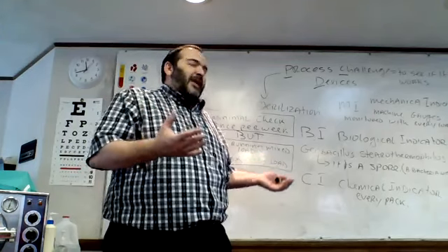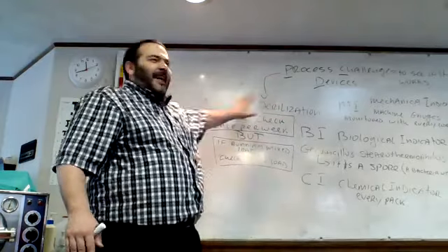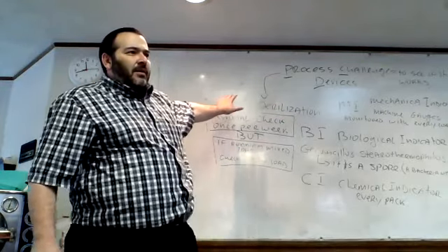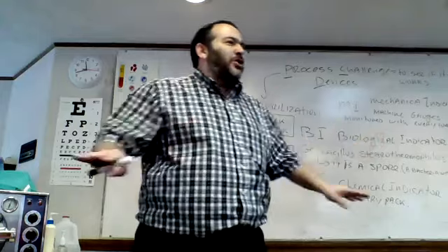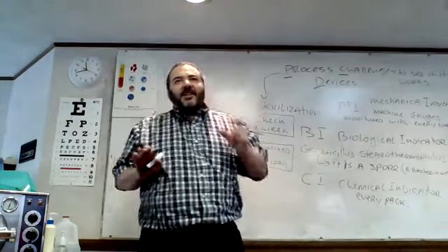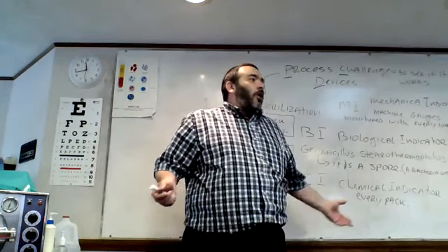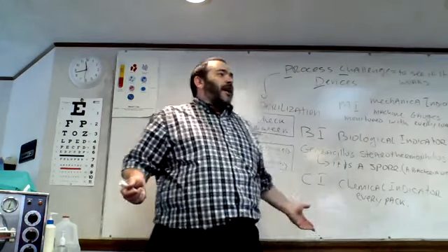If you're running nothing, and I mean all the time, if you don't have anything but stainless surgical steel, I'll give you an example. Your dentist checks their sterilizer with a biological indicator once a week because they don't have anything but stainless surgical steel. Look at their instruments. All stainless surgical steel. So how often do they have to do it? Once a week. If they're really anal retentive about it, they can do it once a day. If they're totally stupid, it's going to cost them a fortune, they're going to do it with every load.